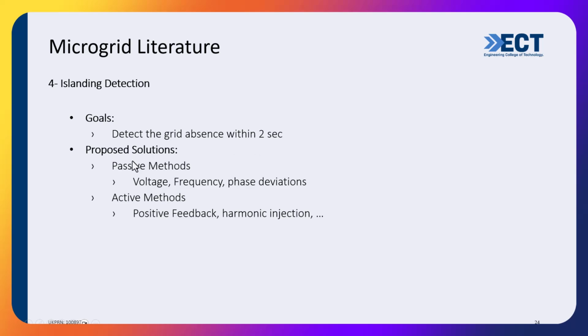There are proposed solutions, for example, passive methods such as voltage and frequency deviation. How do they do that? We know that if the grid is there, controlling the bus, the frequency will not shift at all. It will be exactly 50 Hertz. Even if each inverter tries to shift that frequency, the frequency will not shift because they are dominated by the grid. But if the grid is not there, the frequency will shift. And if the frequency shifts, that is a sign of grid absence. So this is one of the methods.